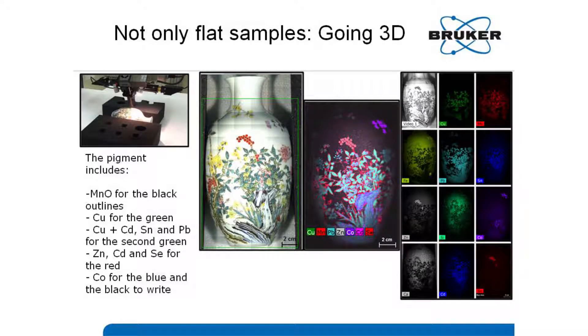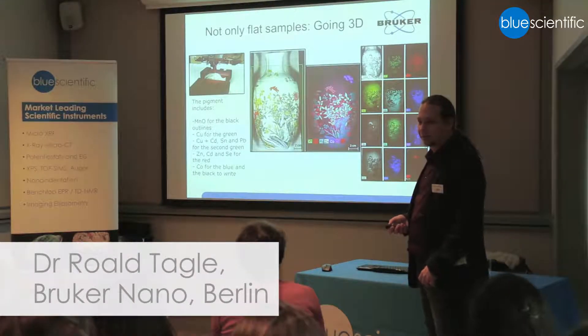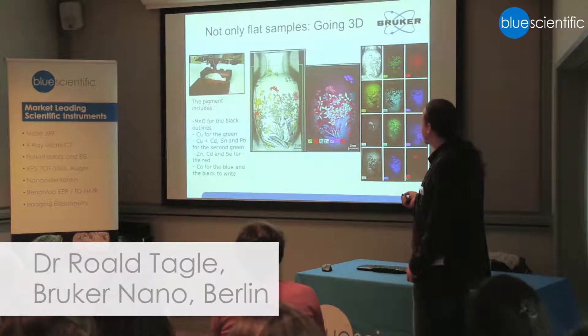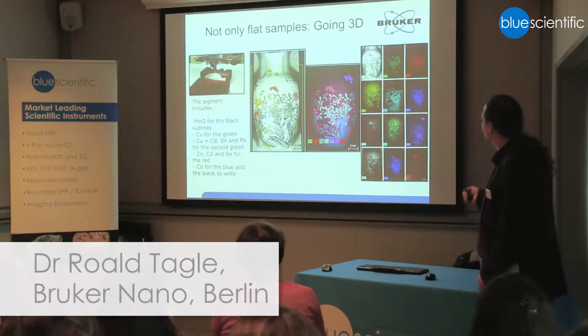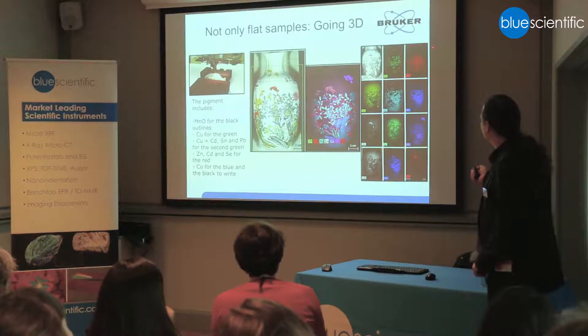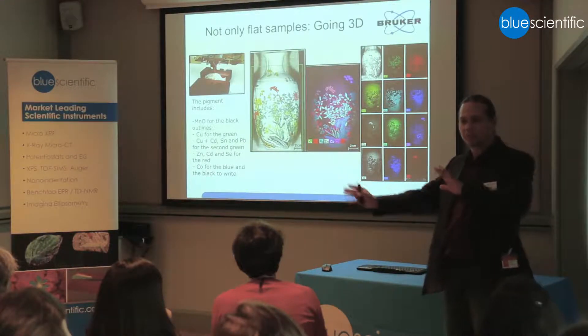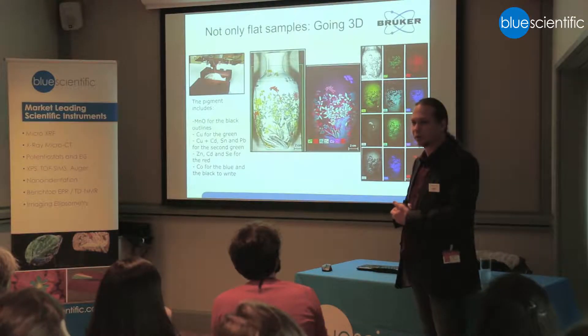The instrument is ideal for flat samples — it loves flat samples. If you don't give it flat samples, you can still get a measurement, even on objects like this which have very strong curvature, like a vase. You can do a scan and then see which element is associated to what type of pigment. You just see when it goes to the edges that there is a shift, but this is a typical thing when you are measuring something on one side.